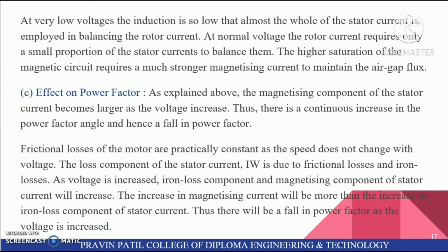Next is the effect on power factor. As explained above, the magnetizing component of the stator current becomes larger as the voltage increases. Thus, there is a continuous increase in the power factor angle and hence a fall in power factor.